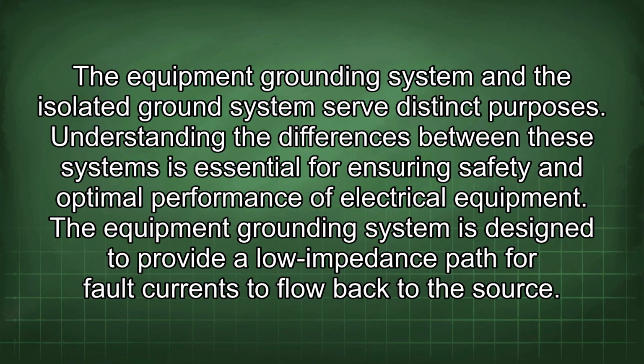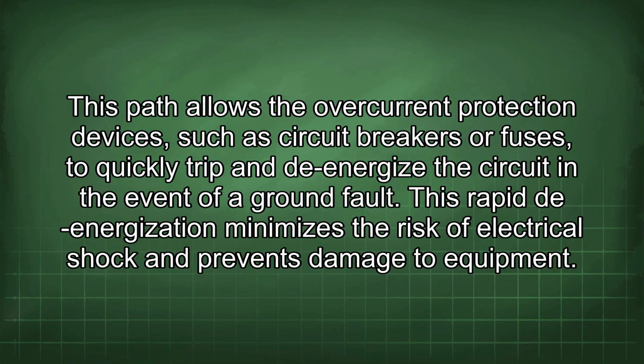The equipment grounding system is designed to provide a low impedance path for fault currents to flow back to the source. This path allows the overcurrent protection devices, such as circuit breakers or fuses, to quickly trip and de-energize the circuit in the event of a ground fault. This rapid de-energization minimizes the risk of electrical shock and prevents damage to equipment.